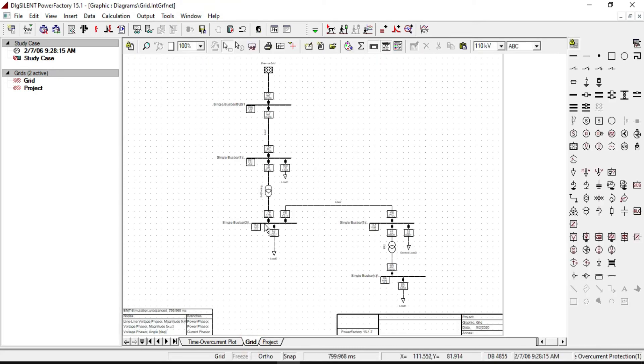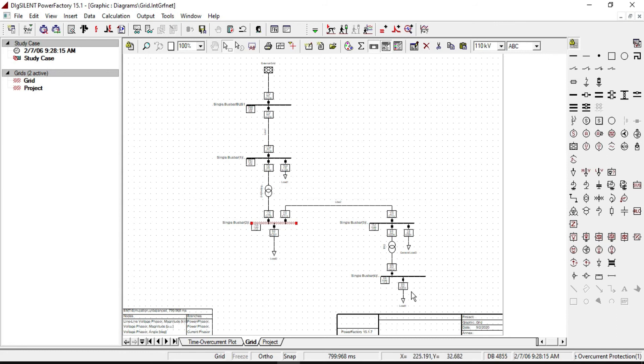Let's look at the single line diagram. The short circuit events were defined on bus 3. When a fault occurs here, all buses downstream from bus 3 will be affected the same as bus 3, since there is no other voltage source connected to those bus bars. In case of fault, all these downstream buses will turn off.